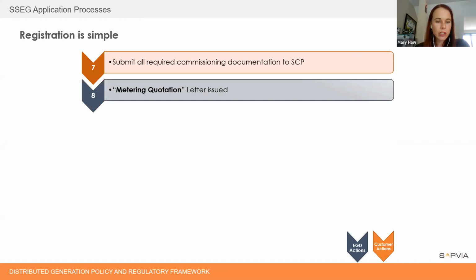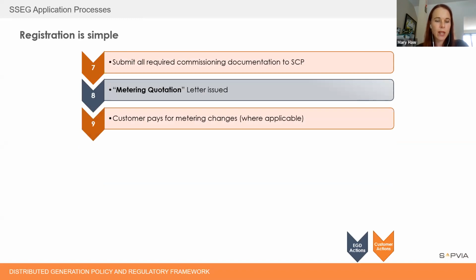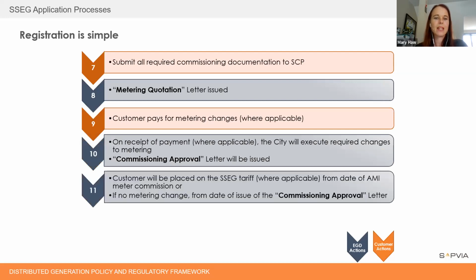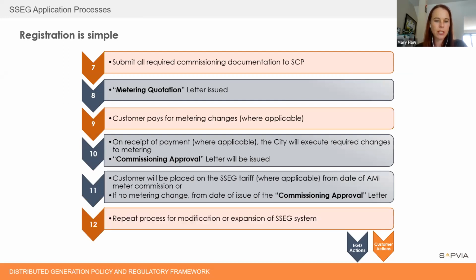And then all of that information and the commissioning documentation goes back to the city, where a metering quotation letter is issued. This is in the case of a feed-in system, grid-tied feed-in system. The customer pays for the meter. Next, the meter gets installed and your commissioning approval is then given. And where appropriate, you will be put onto the correct SSEG tariff. And that's it. Obviously, if you're doing a big change to your SSEG system, you will have to go through this again.